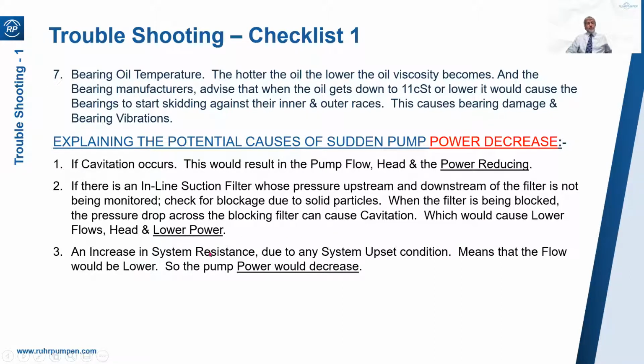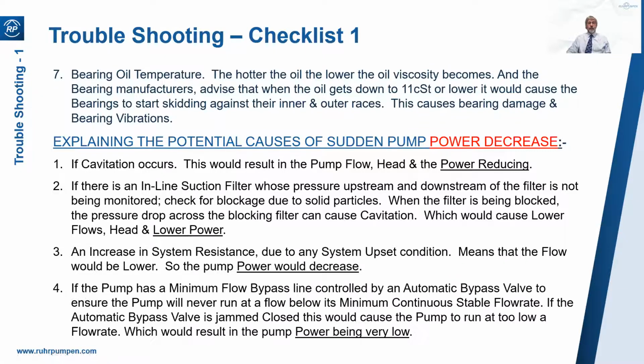Again, look at your system resistance curve. Maybe if your system curve has gone up due to some sort of upset, it might mean that the flow is lower. So if your flow is lower, your power will decrease. And the last one to look at, maybe your minimum flow bypass line has an ARC valve that is stuck shut, in which case the pump will be operating below its minimum continuous flow, a lot of vibration, lower power because the flow is so low.